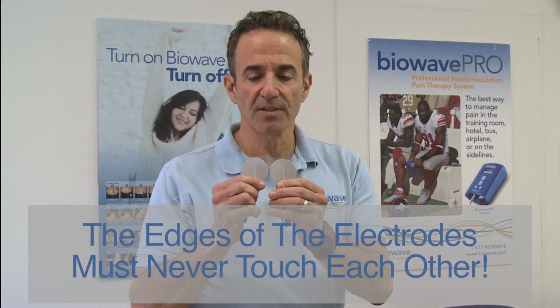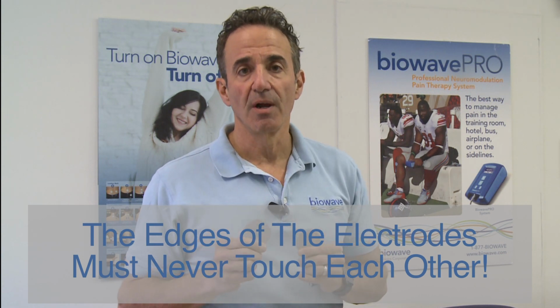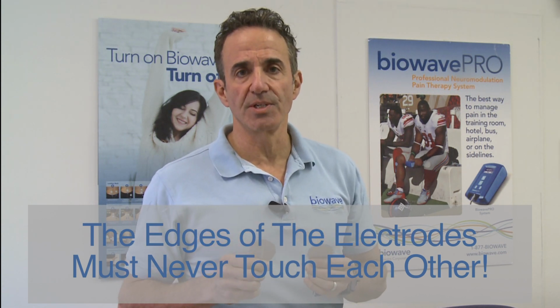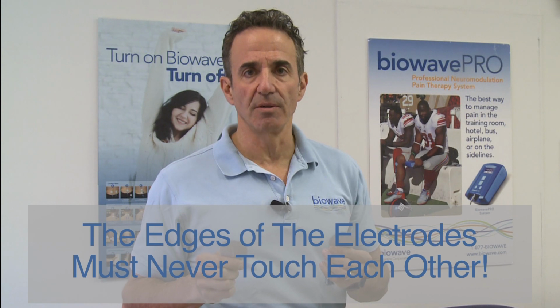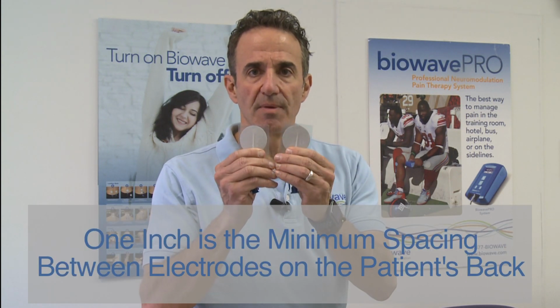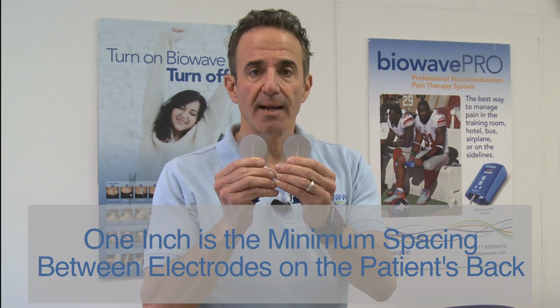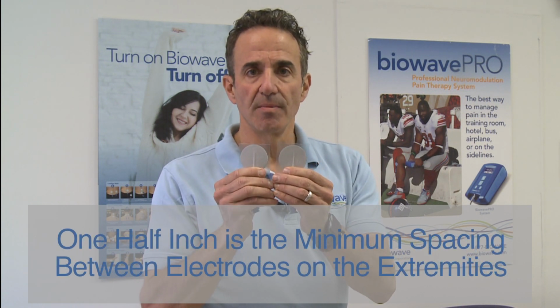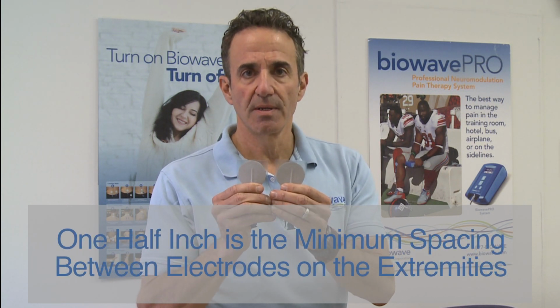Safety. The edges of the electrodes must never touch each other. They cannot physically touch each other. Otherwise, the patient will receive a burn in 5 seconds. It'll be warm, hot, ouch. So 1 inch is the minimum spacing on the back. 1/2 inch is the minimum spacing on the extremities.